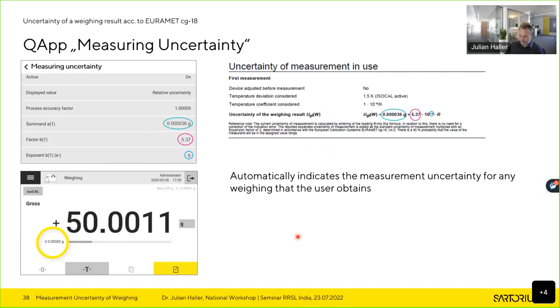And this is really something I should highlight, that as mentioned in the beginning, the user of any measuring instrument is responsible to state the uncertainty of his measuring results. Now this is quite complicated, as you have seen on the previous slides, but you have the possibility to make it easy for you. Just get a calibration certificate from a respective calibration lab, enter these values into your balance, and then you will get the uncertainty directly with any weighing result. So it can't be easier for you.